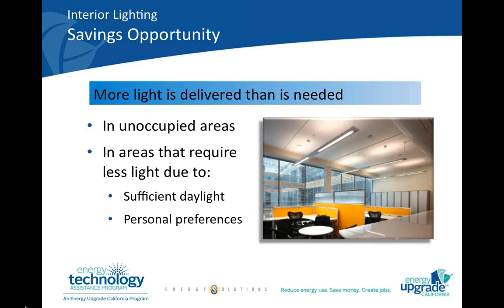The savings opportunities from wireless lighting controls come from the fact that typically interior office spaces usually have little functionality and controllability of their lights beyond basic on-off capabilities, and sometimes control by time clocks. So at the beginning and the end of the day, the lights will come on and come off at a set time. This really leads to the opportunity to reduce light levels on a fixture-by-fixture basis according to occupant preference, daylight potential, smart scheduling, etc.